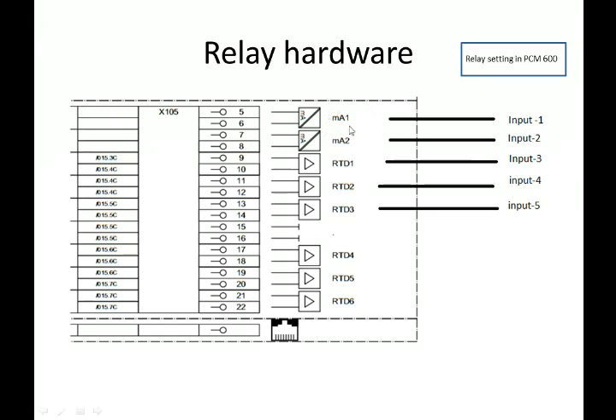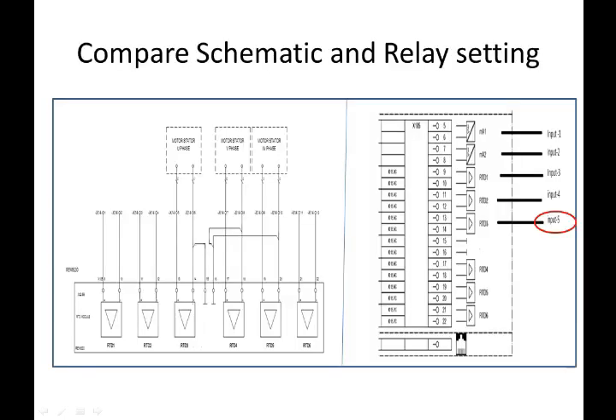According to this relay, settings will have input 1, input 2, and so on. Now I'm going to compare the relay settings and schematic. According to the schematic, the winding RTD starts from 3, but for relay settings it will start from input 5, since the first two are for mA sensor.